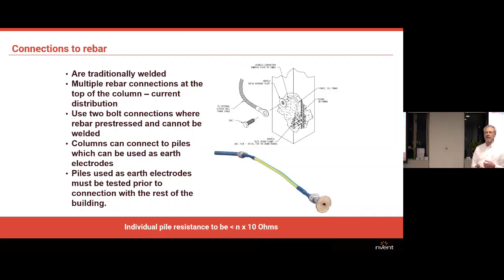CAD weld, for those who don't know it, is an exothermic welding process for electrical connections, and it is maintenance free and the best connection you could possibly make for electrical performance. Ideally, in a situation where you're going to bury connections, you CAD weld it, better than clamps. That can be argued, but CAD weld to rebar can be difficult. So using the CAD weld connection of the steel tip, or the steel lug, they call it, on the end of that cable, CAD weld that to your normal green earth wire, and then at this end there can be a terminal block or terminal plate that can be set into concrete, so you can screw your earth connections to it, or you can get it with a bare tail at this end, so you can make your own connection with that green earth wire.